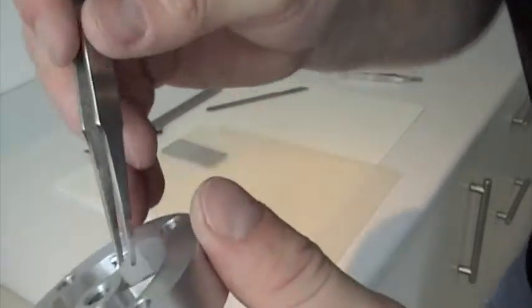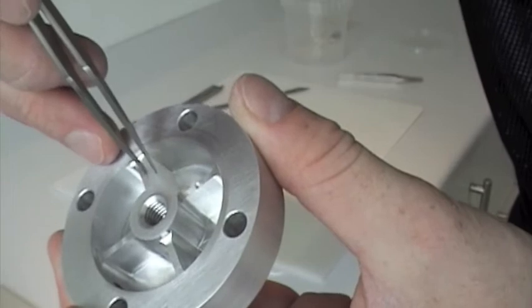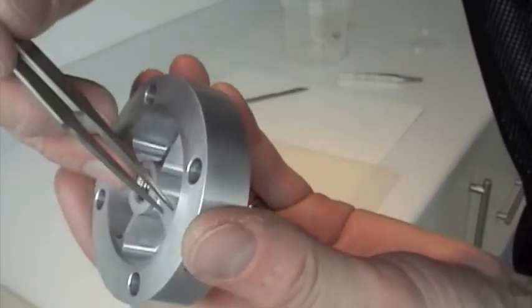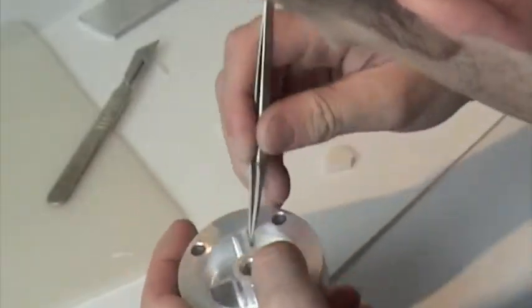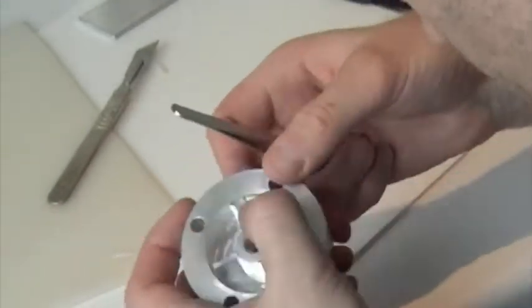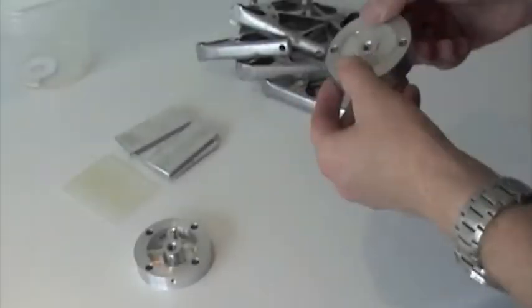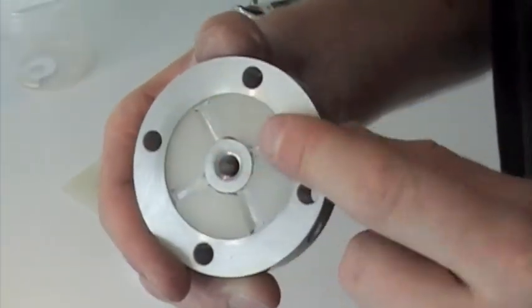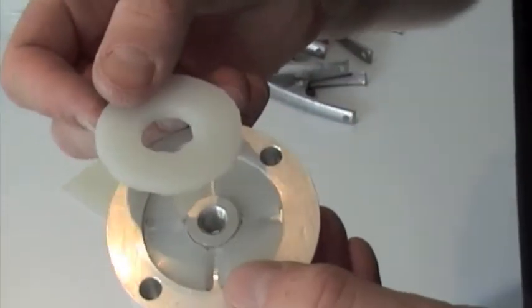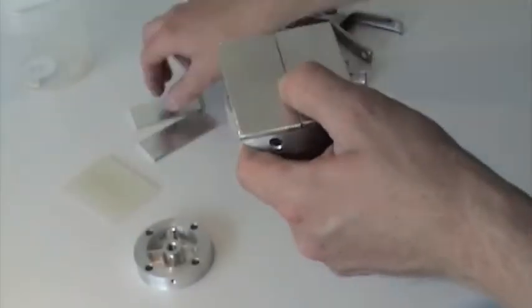Hi, I'm Andrew Becks from StrainTech. This is the second video in the series demonstrating the preparation of the clamps we will be using to clamp strain gauges to the Bloodhound SSC load cells. In this video I'm trimming high temperature rubber sheets to custom fit the strain gauge areas on the load cells. The strain gauge areas will be packed tightly with the rubber and then clamped using aluminium strips and various spring clamps in an even pattern.